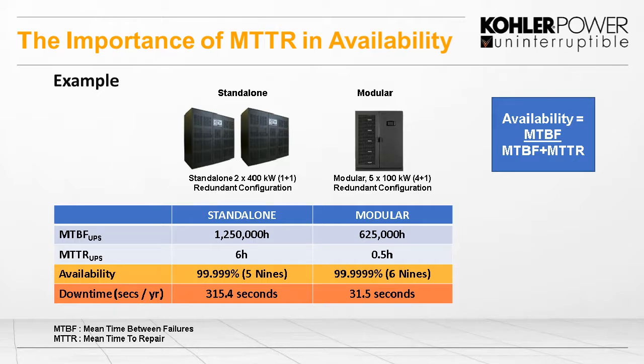And when we look at this example here, we can see an N+1 system, in this case 400 kilowatts, 1+1, that's got a typical mean time between failure of 1,250,000 hours, compared with 5 modules of 100 kilowatt, which, obviously with more modules, we have a lower MTBF at 625,000 hours. However, as we've explained, the repair time for a standalone can be 6 hours easily. And for modular, it can be well under half an hour.